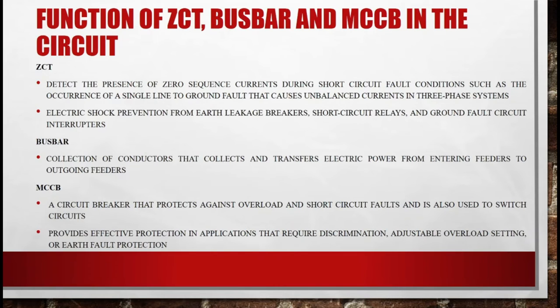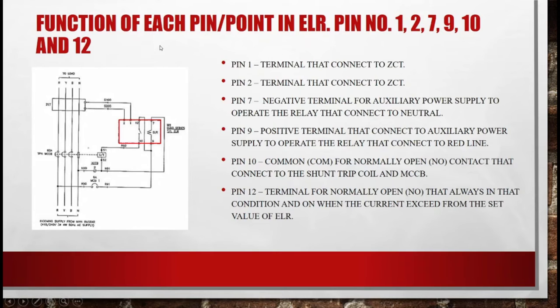MCCB trips if it detects a short circuit or an overload in the circuit for an extended length of time. It provides effective protection in applications that require discrimination, adjustable overload setting, and fault protection. Now I will explain the function of each pin or point in the ELR.